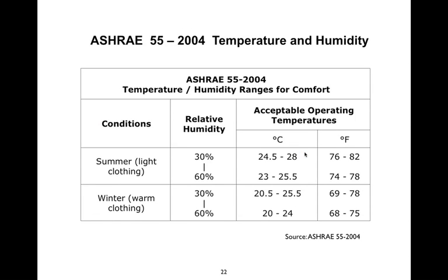For comfort, ASHRAE says summer and winter you want a humidity range of 30 to 60 percent — you don't want the air too dry. They have two different temperature ranges for summer and winter that most people will find comfortable, ranging from 68 up to the high 70s depending on the time of year. Wintertime has a lower acceptable range because people generally wear more clothes in winter.